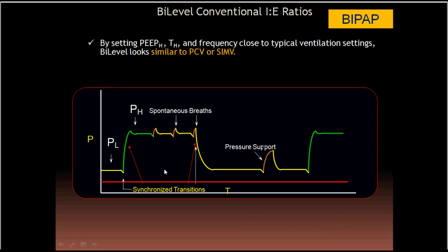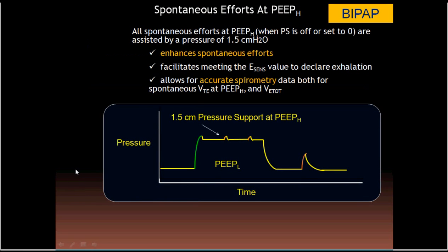For patient synchronization, when the patient starts to take a breath concomitantly with the cycling, he will trigger the high CPAP phase and go up at the same time. The inspiratory wave can be ended based on the patient's effort, providing some synchronization with the patient through this technology.